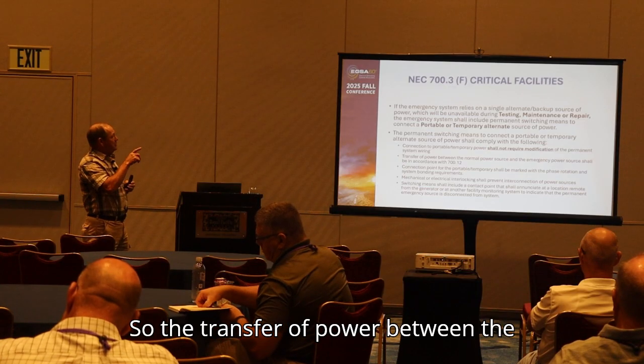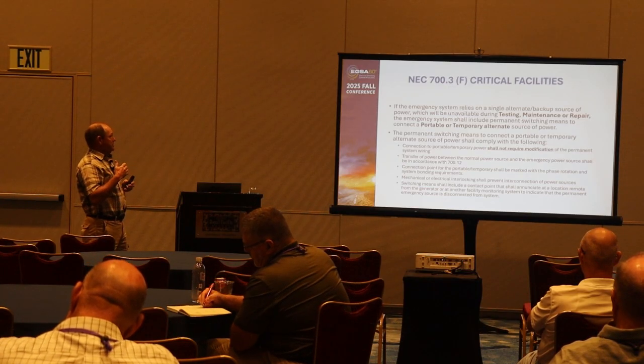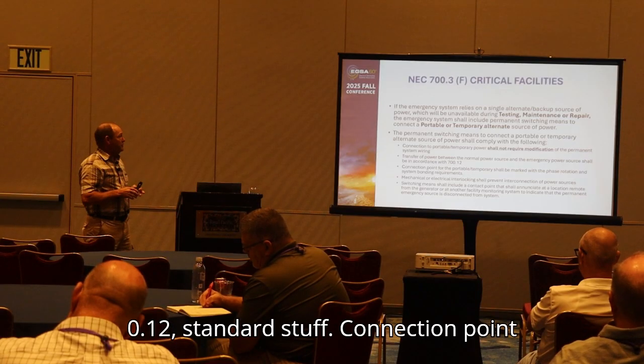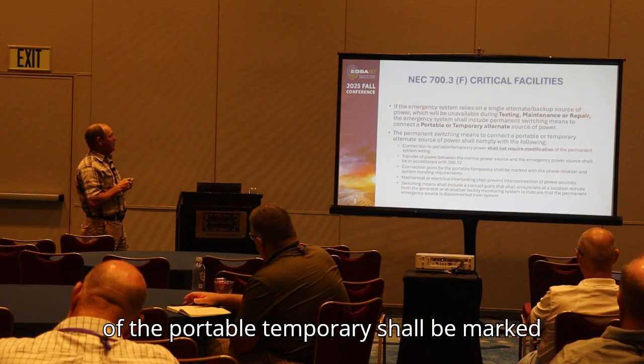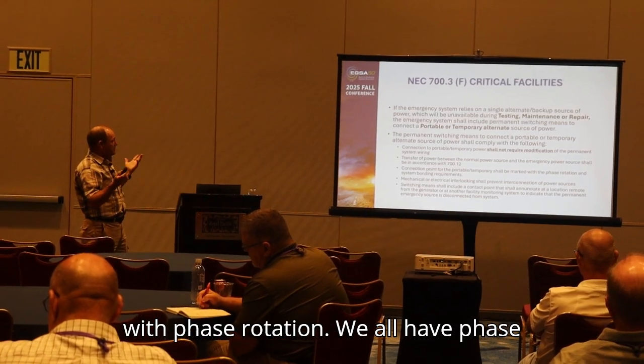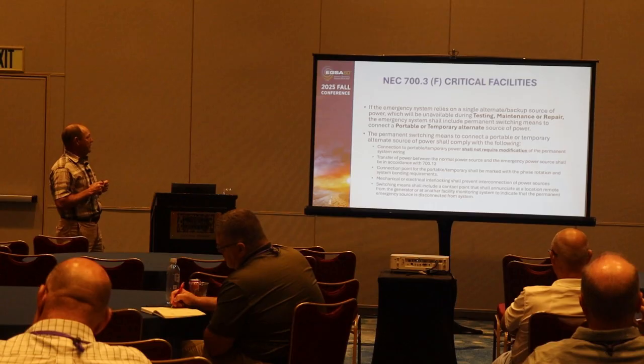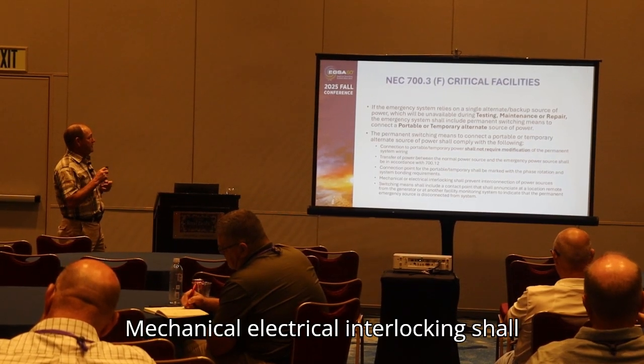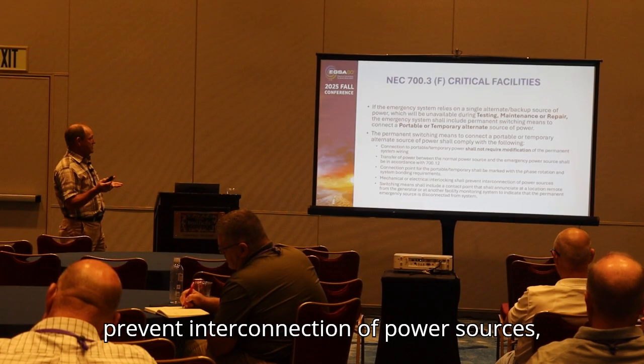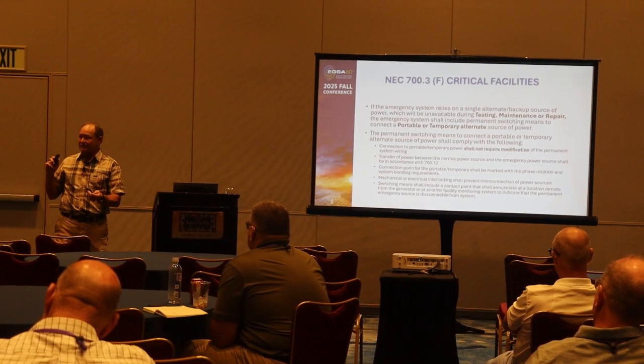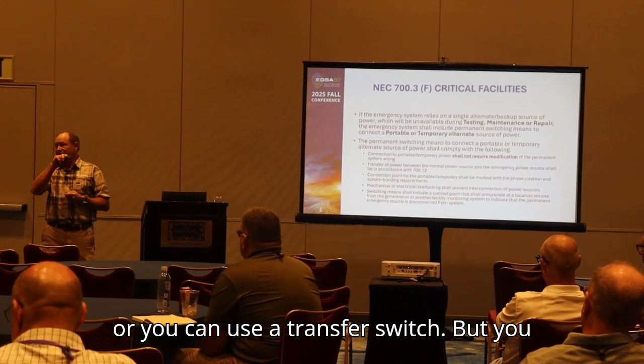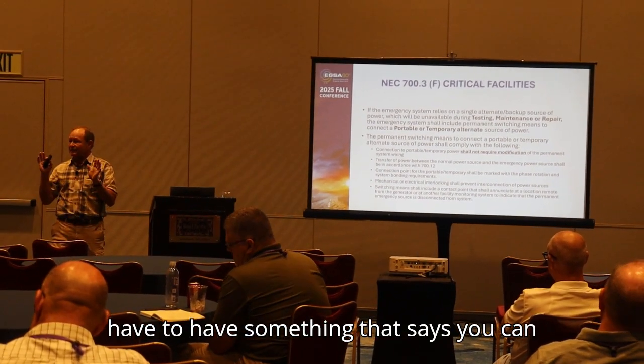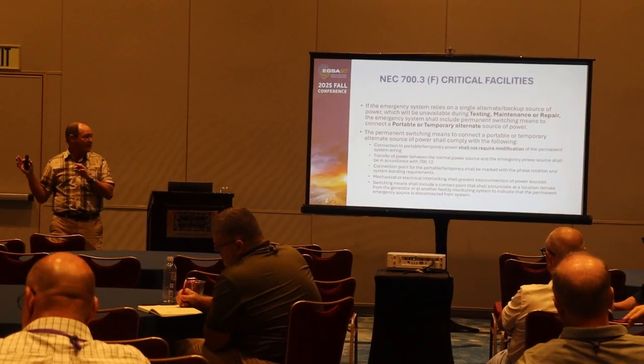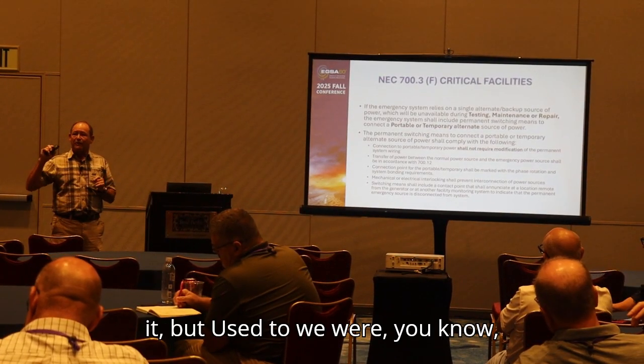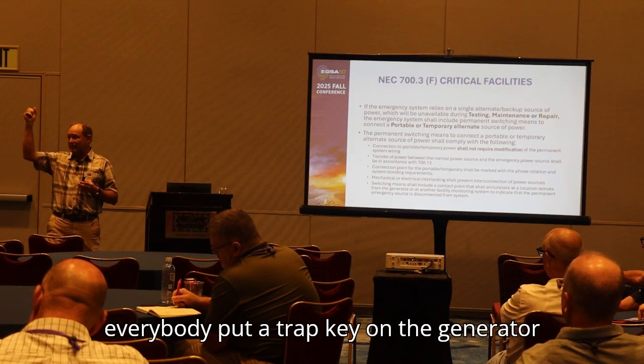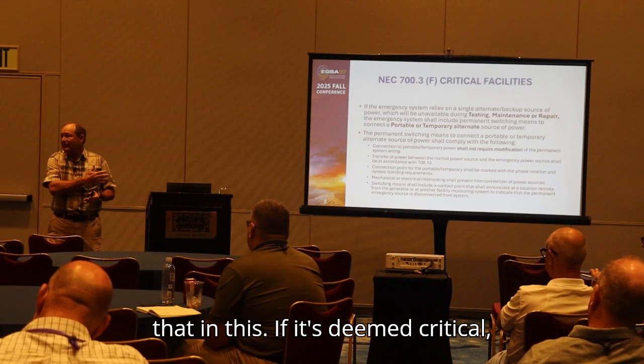So the transfer of power between the normal source and the emergency source shall be in accordance with 700.12, standard stuff. Connection point of the portable temporary shall be marked with phase rotation. They all have phase rotation monitors in them. Mechanical or electrical interlocking shall prevent interconnection of power sources, which means you can use a trap key or you can use a transfer switch. But you have to have something that says you can't do both of these at the same time. I don't know if this has the one line in it, but it used to be everybody put a trap key on the generator. You can't do that in this.